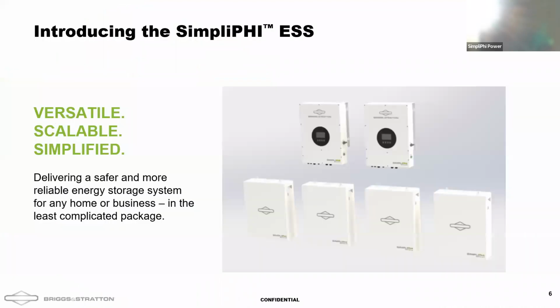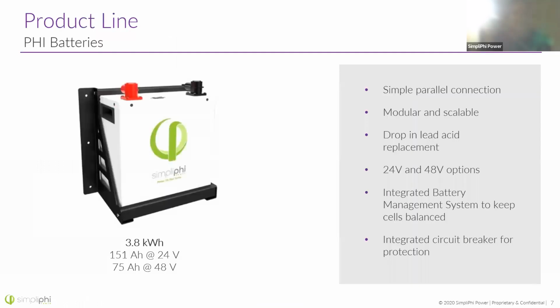Moving into our products, we have introduced a SimpliPhi ESS, an energy storage system, which consists of an inverter as well as a new series of batteries. These are 4.98 kilowatt hour batteries, just under that 5 kilowatt hour need. These are outdoor rated NEMA 3R enclosures, so they can be mounted on outside walls. You have to pay attention to temperature, just like any lithium battery, but these are wall mountable, with a mounting bracket included with both the inverter and the batteries. These might be a good solution if you're looking for a bigger battery starting block for an install.